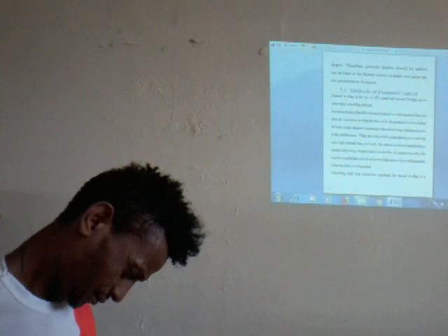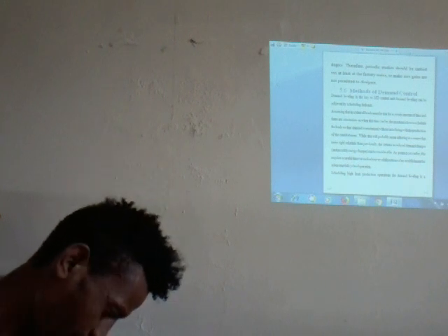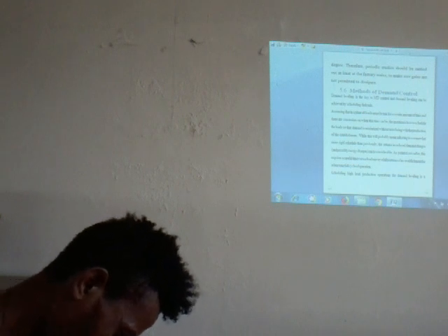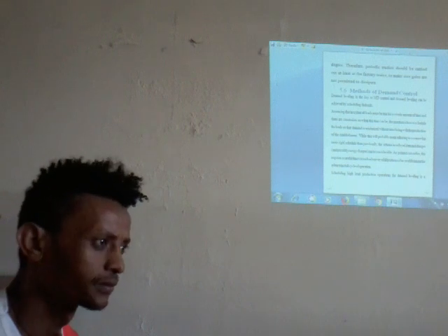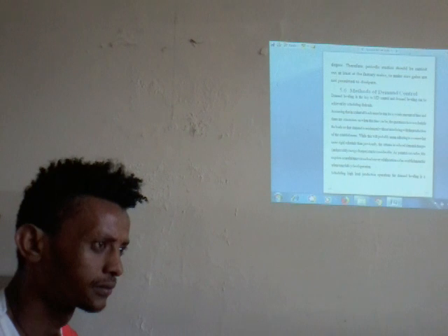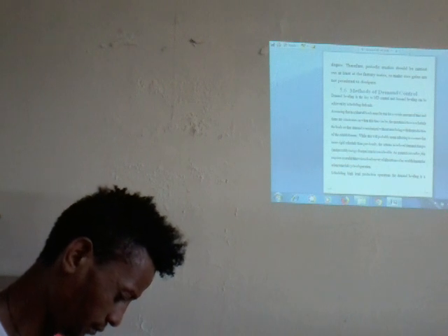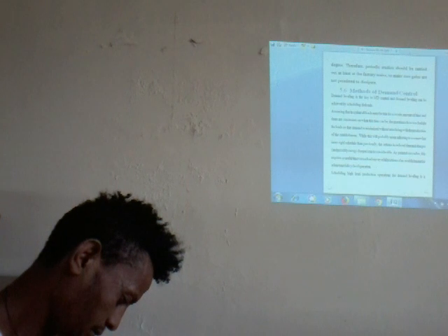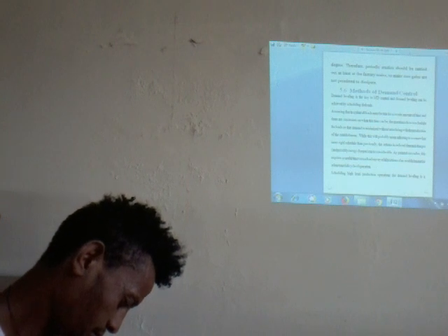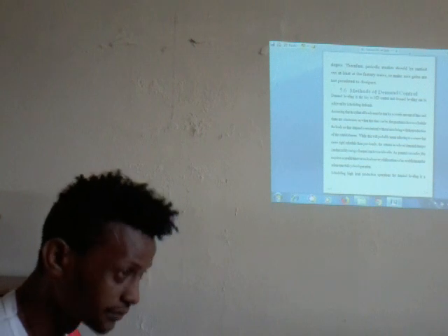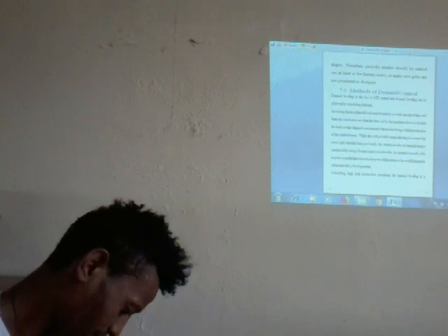The consumer, that means the owner of the pump, thinks the kilowatt hour consumption is not correct. But the electricity board says this is correct. So an auditor goes there and measures the voltage, 430 volt, the current, 25 amps, and the power factor, 0.8. So as an energy auditor, how can you conclude this?